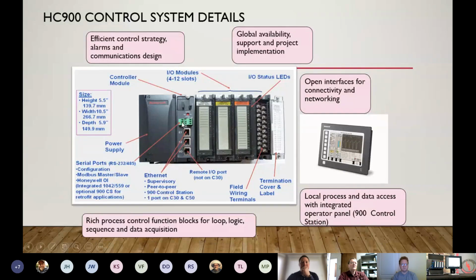Down through the middle of the CPU, you have two RS-485/232 ports. This can be used for a number of different things. One of the main things it's used for is communicating to third-party devices out on the plant floor that might have Modbus communications. So you could actually tie in UDC controllers, Honeywell Herculine actuators. You can tie in paperless video recorders if you wanted to, but there are a lot of different options that serve up as part of the functionality of the HC900. It's very versatile, and like I said, it is a 3-wire RS-485 half duplex, but it gives you the 2 ports there.